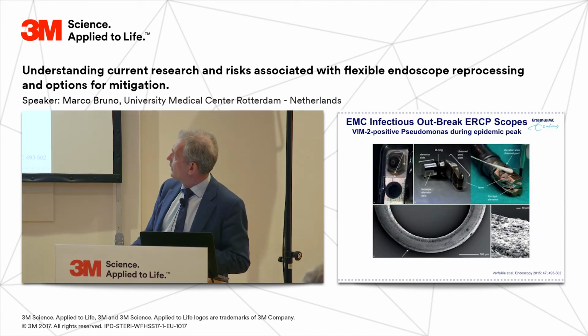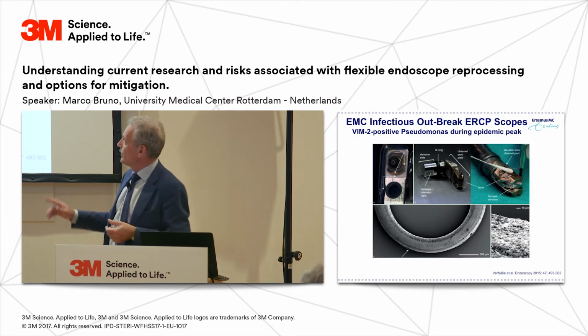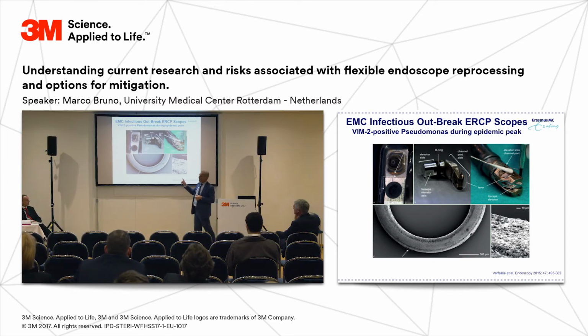And to show you a little bit more in detail, you can see this is a new scope, only used in about 50 patients, and already you see corrosion around the lens of the scope. This is the elevator, and this is the O-ring that is supposed to closely seal off the outside world from the inner working channel where the guide wire is running to move that elevator. But you see all kinds of cracks and indentations, and we found fluid behind the O-ring that also contained the bacteria.